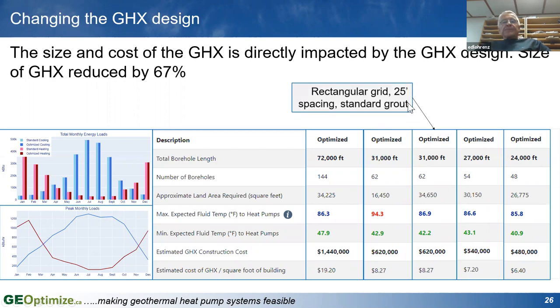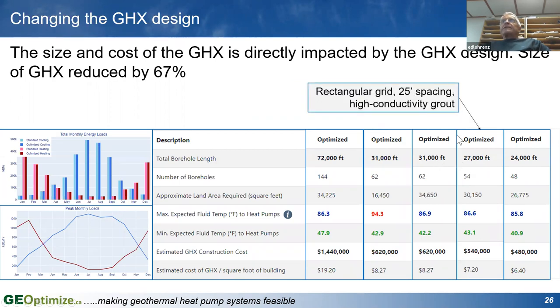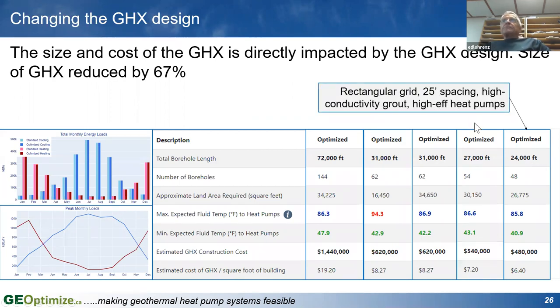Some other things that can be done is change the spacing between the boreholes. Again, in this case, it didn't change much. Here, looking at putting more conductive material in the space around the borehole, so the heat transfers to and from the pipe more readily, dropped it another 4,000 feet. Here, we're looking at installing more efficient heat pumps in the system, and that changes how much compressor energy has to be shoved into the ground versus how much heat has to be extracted from the ground when the system is heating. That's dropped it down from 72,000 feet to 24,000 feet, simply by how the ground heat exchanger is designed. So rules of thumb really can't take into consideration all of those different variables with any kind of accuracy.